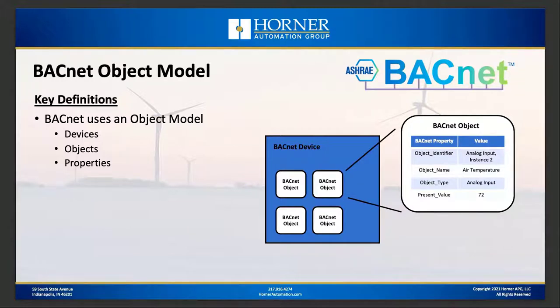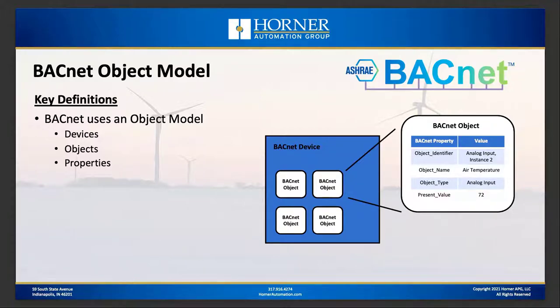Let's talk about some key definitions you need to know when working with BACnet. Like a lot of protocols, BACnet uses an object model. A BACnet device is made up of multiple BACnet objects, and those objects are made up of multiple properties. So we start at the device level, within that we have objects, and within the objects we have properties.